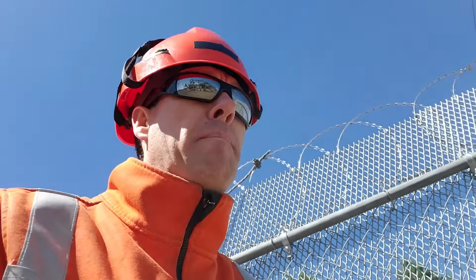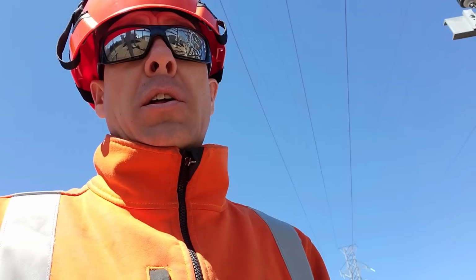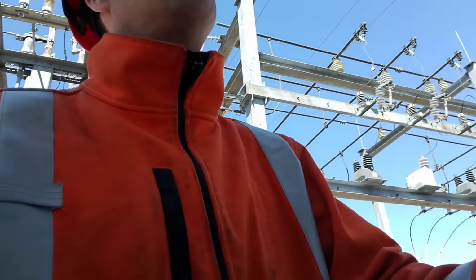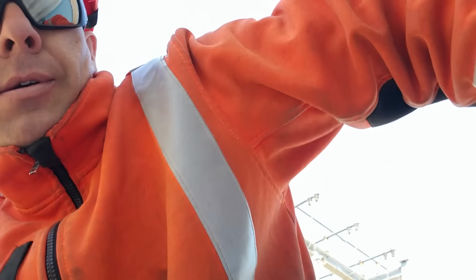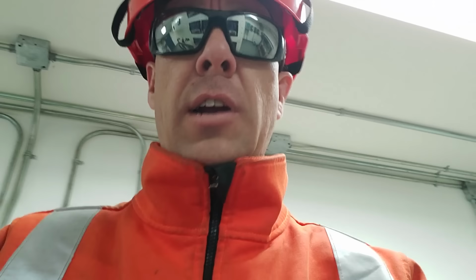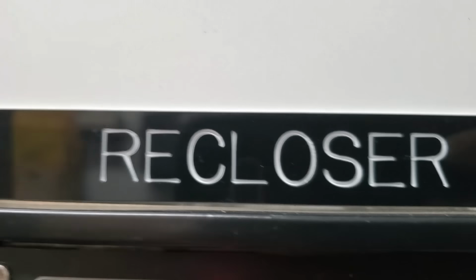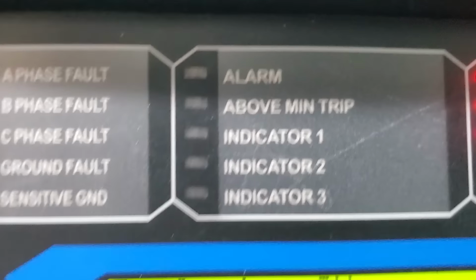Alright, so we are back at the substation now. We're going to remotely close that recloser in from inside the building. And I'll show you guys what I personally like to do when picking up a line like this, especially 800 customers. So we're going to light up our screen. Just hit enter. We do have to verify, once again, we have permission to close in our recloser 6518R003. So we are at the right location.